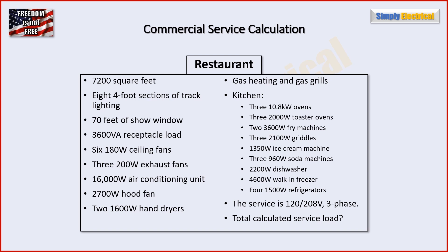Here is our example. We have a restaurant — 7,200 square feet. We've got some lighting track, some show window lighting, a receptacle load given to us, some ceiling fans, exhaust fans, an air conditioning unit, a hood fan, and some hand dryers. Our heating is gas — that's important — and our grills are gas as well. Then we have our kitchen equipment, which we'll get to as we put it into the calculation. Our service is going to be 120/208 volt three-phase, and we're going to find our total calculated service load.